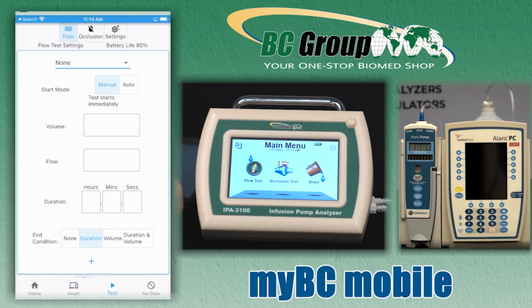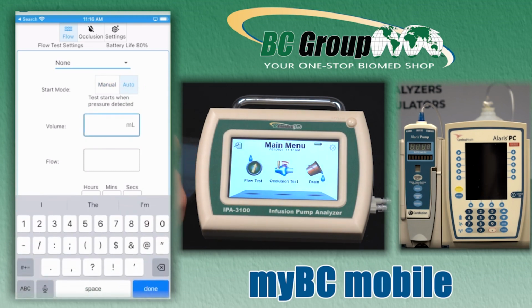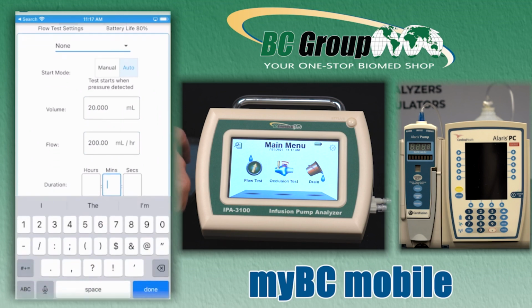So then we have to select, how do we want the test to start? Is it going to be an automatic start? So this tells it as soon as the flow is detected to start measuring the flow rate, or the manual selection. And that starts the timer. As soon as I hit start, it starts the timer and starts collecting data. And I'm going to set my volume at 20 milliliters. And if we run at 200 milliliters per hour, that test should take 6 minutes.